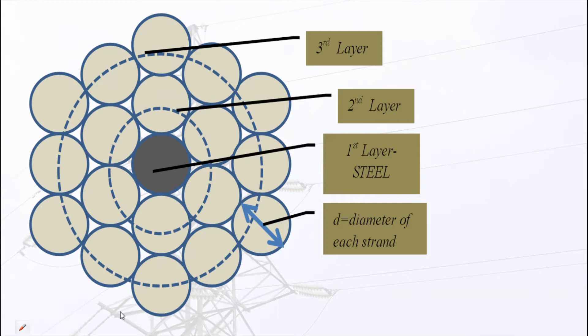Now see this diagram of the stranded conductor. You can see that it has three layers. The gray colored central strand is made up of a different material — steel — which improves the overall mechanical strength of the conductor. The outer two layers are made up of several aluminum conductors, and these aluminum conductors perform the main function of carrying current.